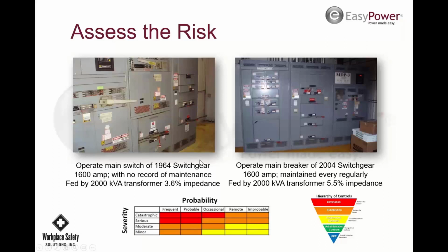And then Simon has one question before you go further. Okay. Do the pump starters require labels? If I'm feeding anything with a breaker that's greater than 50 amps, I'll probably put a label on it. So it depends on what size pumps there are before I decide if I want to label it or not. But if I suspect that the arc flash level is going to be higher than zero, what used to be called zero, if it's over 1.2, I would probably put a label on it.